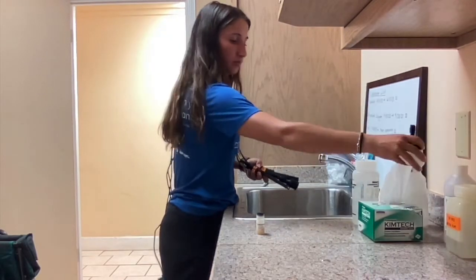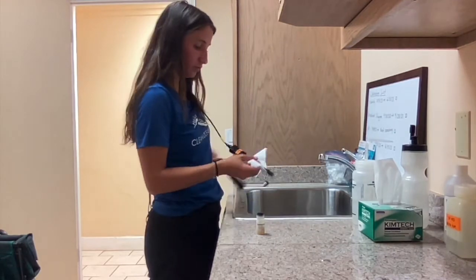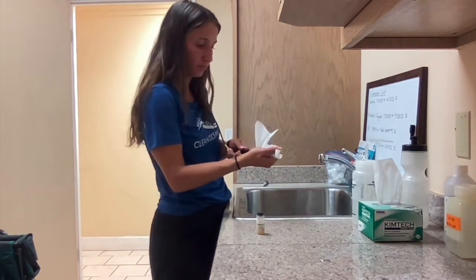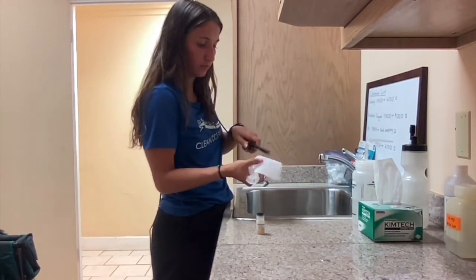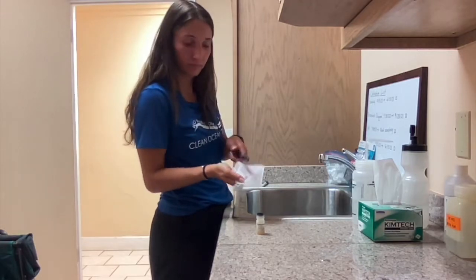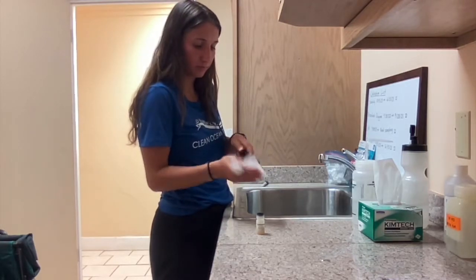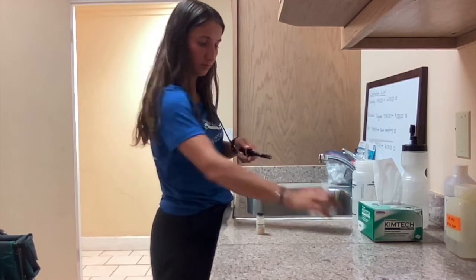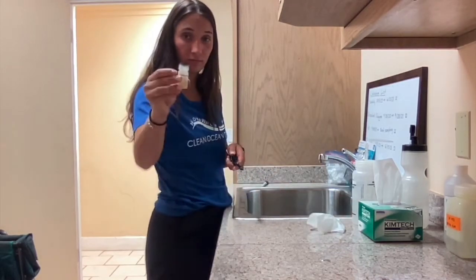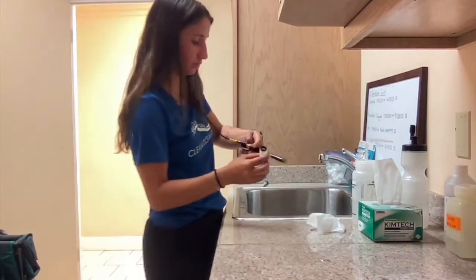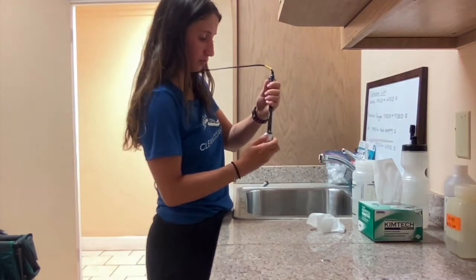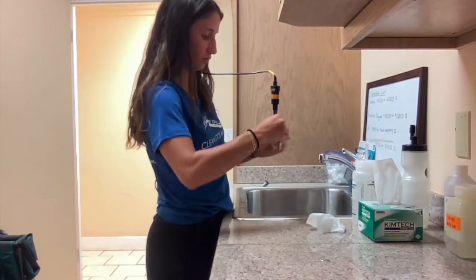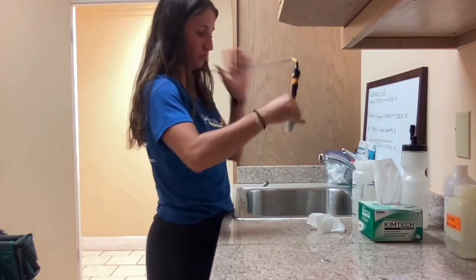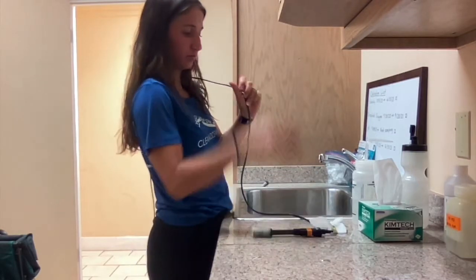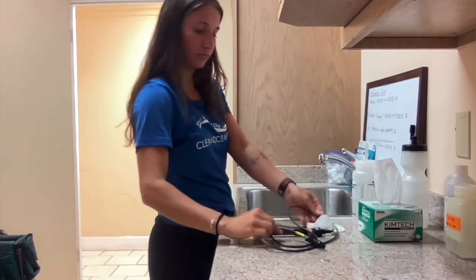Dry all of the probes with Kim wipes and then tap the sensor side of the probe gently on your Kim wipe covered palm to ensure excess water is removed. Then place the pH probe back into the KCl vial and tighten so no solution spills out. Place the probes in a secure place for transport to the next site where they will be ready to use without further rinsing.